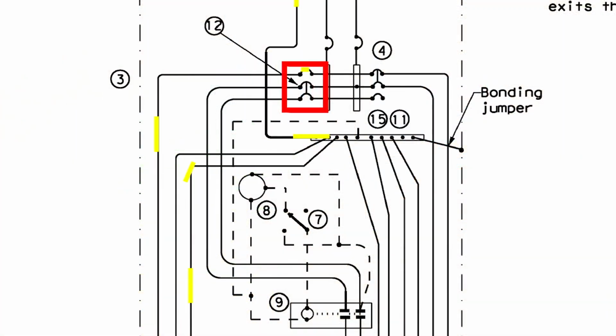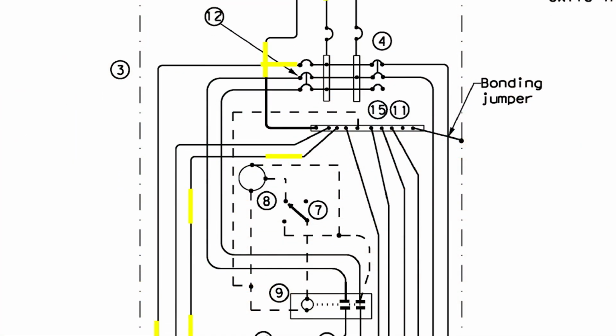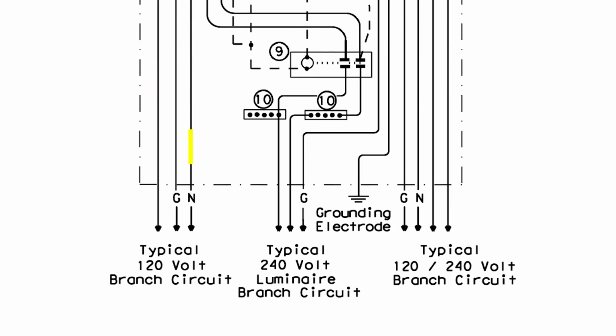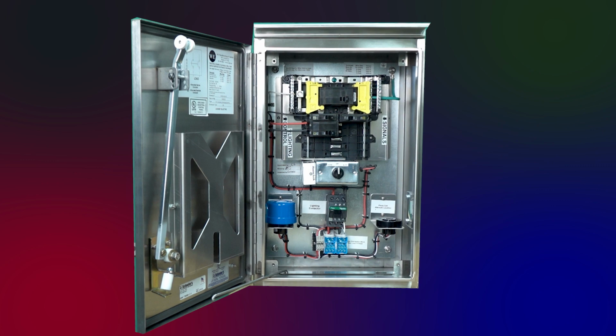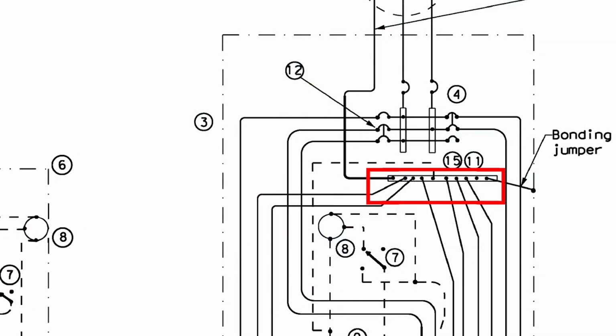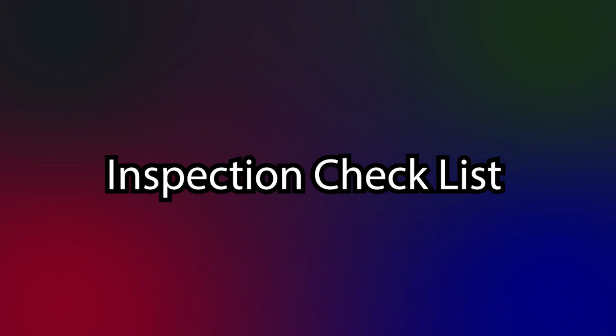A Type D service will have some loads, such as a signal cabinet or flashing beacon operating at 120 volts. Each 120-volt circuit in a Type D service will include a conductor with a white-colored insulation. As can be seen in the schematic diagram, white and green insulated conductors and bare copper conductors will all be connected to the grounding bus bar. Let's now review an inspector's checklist for the Type D electrical service.